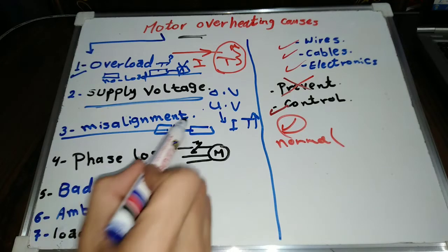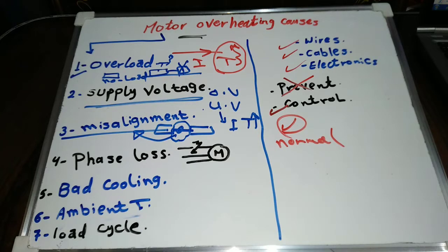Load misalignment. Mechanical loads and the electric motor are shaft-to-shaft connected through a coupling. It's the mechanical team's job to make sure the motor and load shafts are in good alignment. If not, the motor will face larger mechanical load and will overheat.